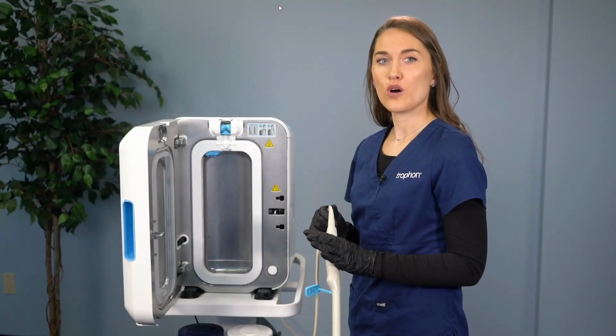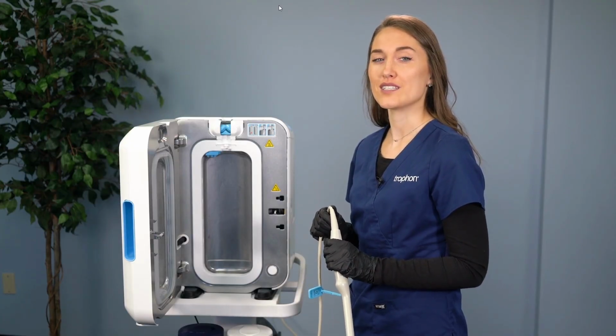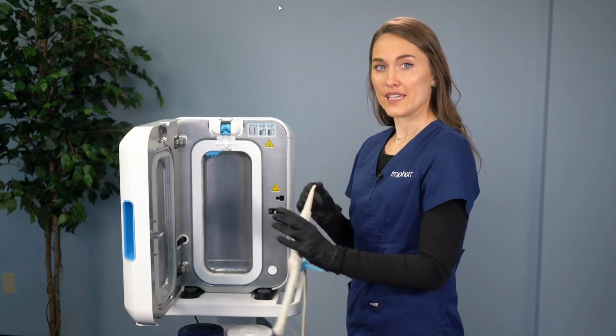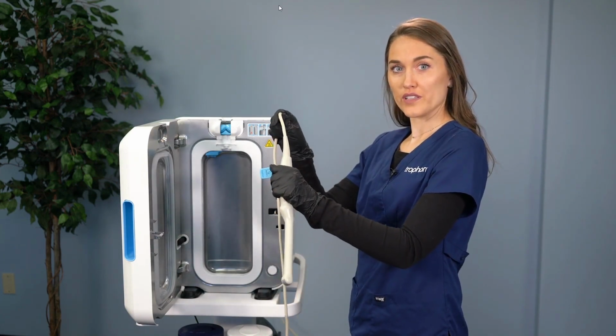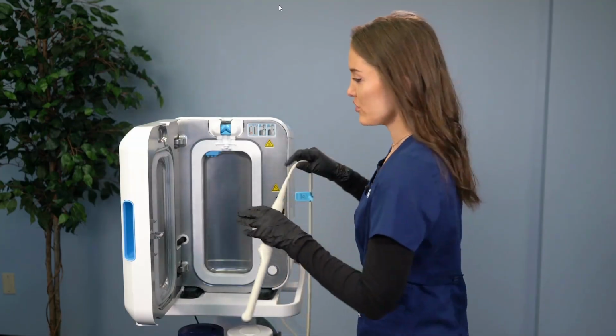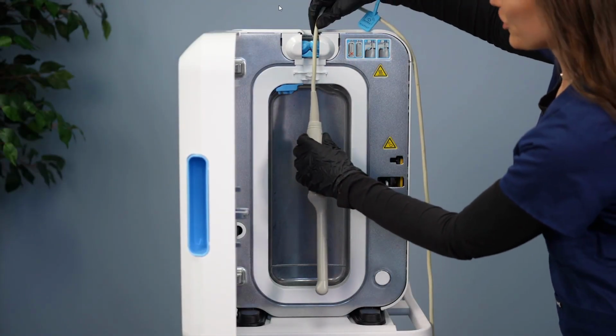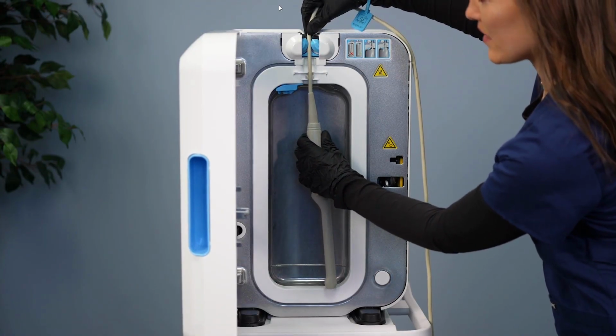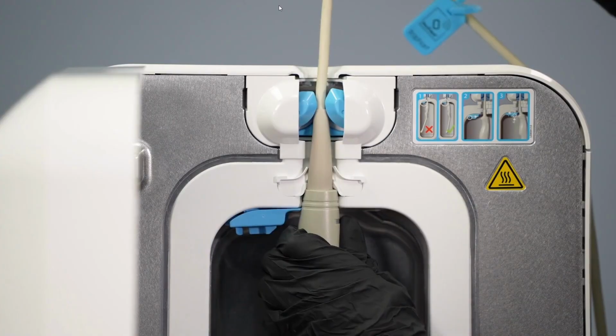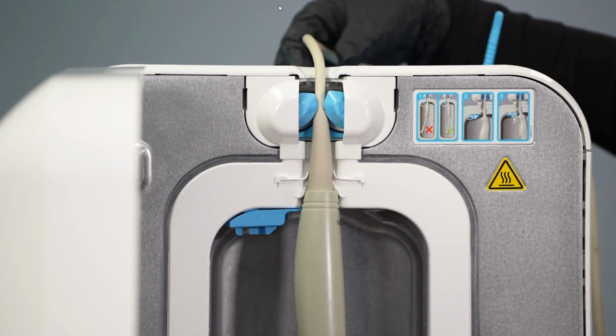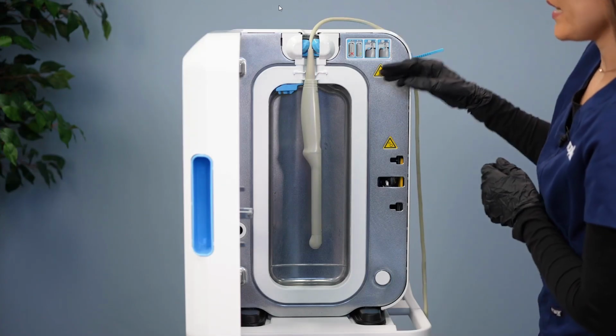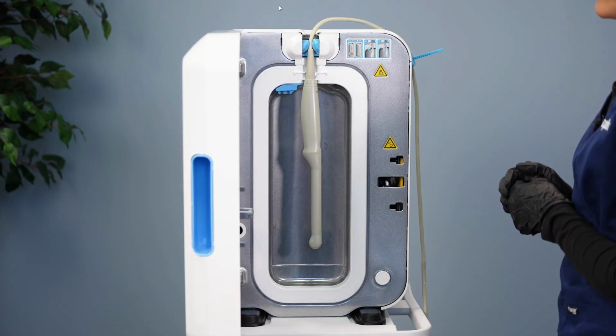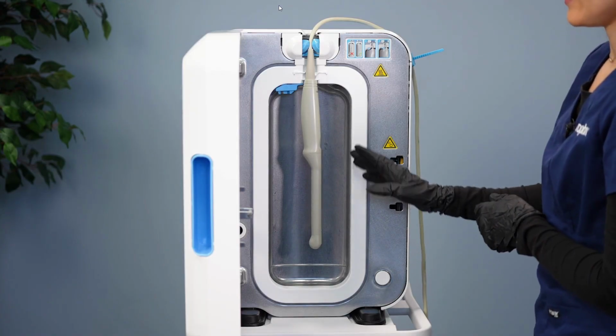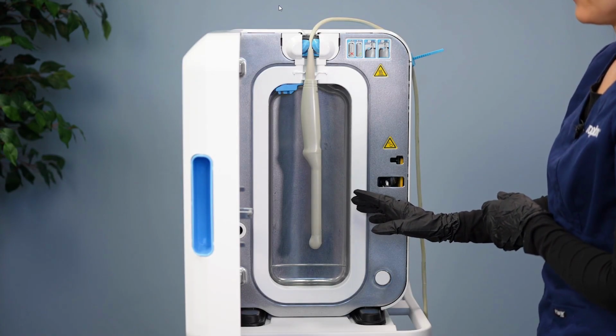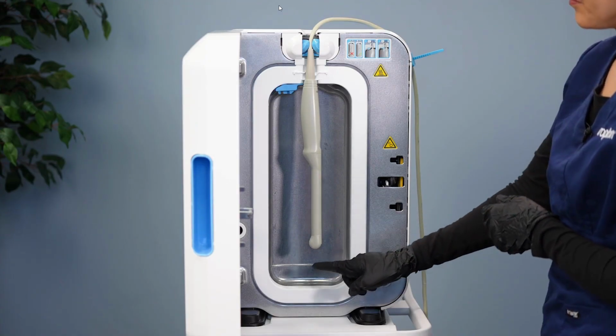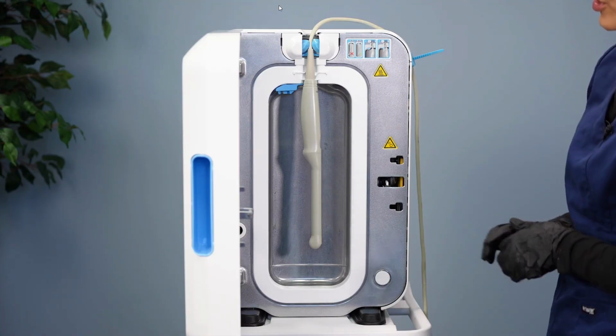Now, when loading the probe, you always want to use a two-handed technique so as not to damage your cord. You want one hand on the probe handle and one on the cord itself when loading the probe. So you can start low in your chamber, push into the cable clamp, and as you're doing that, pull up on the cord gently, and it should guide into place. There is a white cable seal where your strain relief should sit. Make sure the probe is not touching any of the sides of your chamber and that the tip of an endocavitary probe stays above the embossed line at the bottom of the chamber.